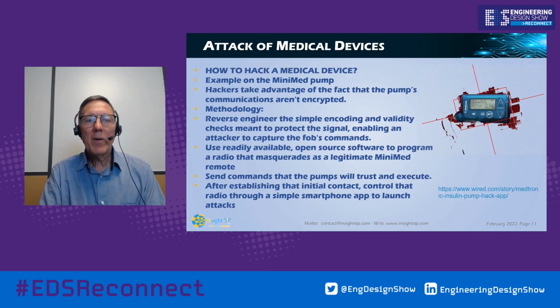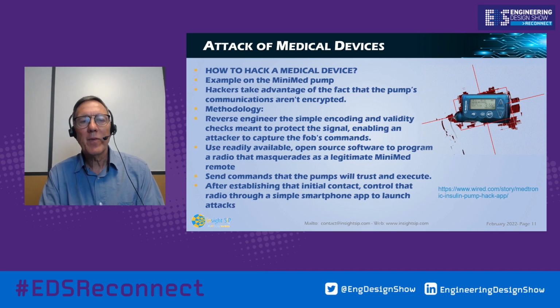So how do you hack a medical device? This is a different device. It's a MiniMed pump from a different manufacturer. They took advantage in this case of the pump's communications, which are not encrypted. And the methodology was to reverse engineer the encoding and the validity checks that were meant to protect the signal. And then they used open source software to program a radio that looks like the legitimate MiniMed remote, sends commands that the pumps will trust and execute. And once you've made the contact, you can do anything you like with the pump. So that's not a particularly good thing to have.